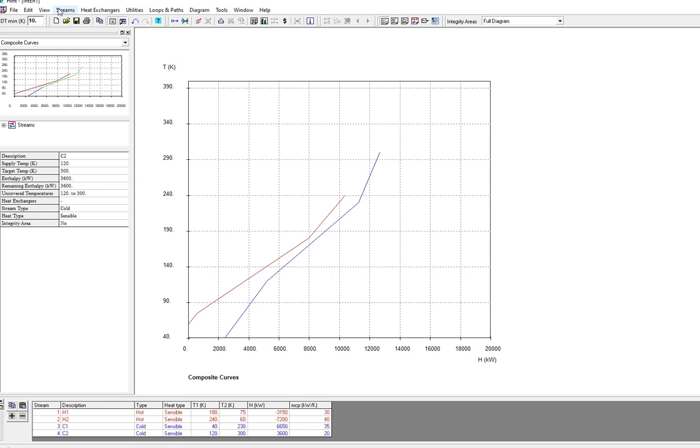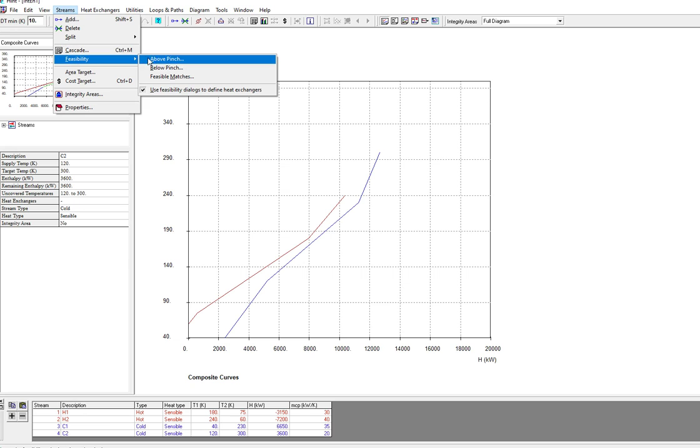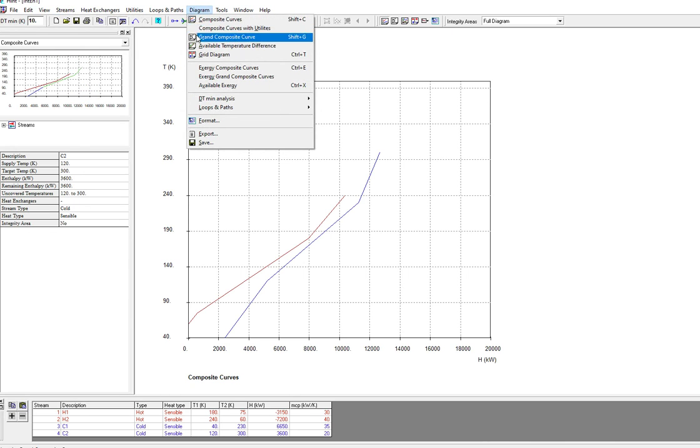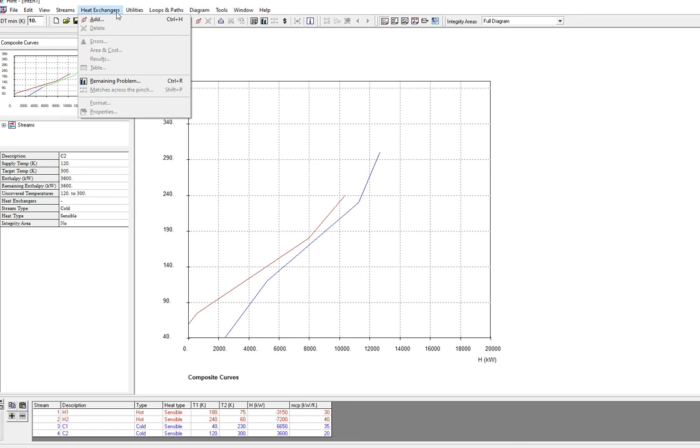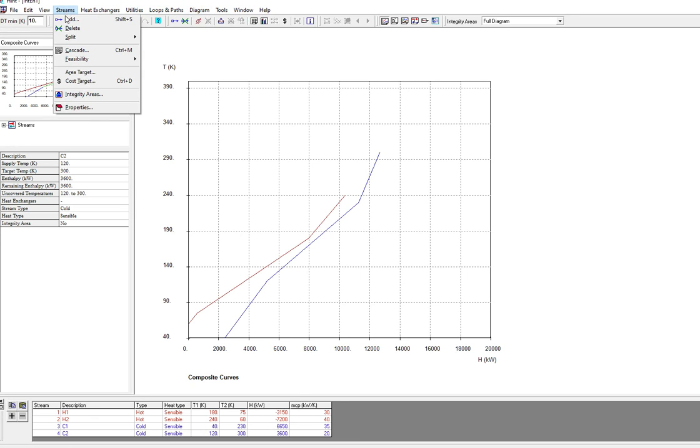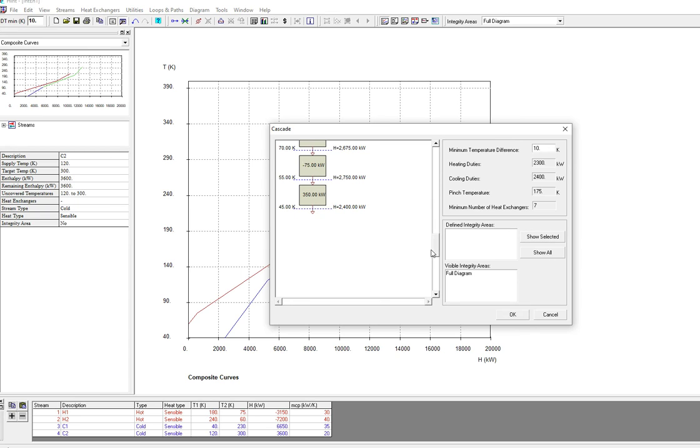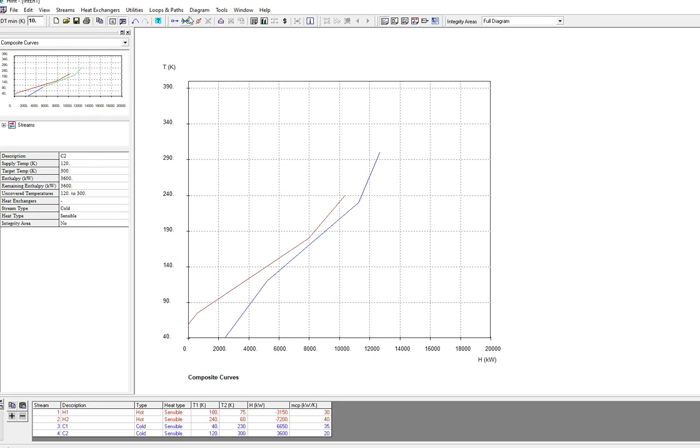After that you can see the pinch values or cascades. If you go to the cascades, it shows the minimum heat requirement and the minimum cooling requirement. It shows the minimum temperature difference delta T, the heating duties, cooling duties, and the pinch temperature at 175. For this data, the minimum number of heat exchangers required is seven.